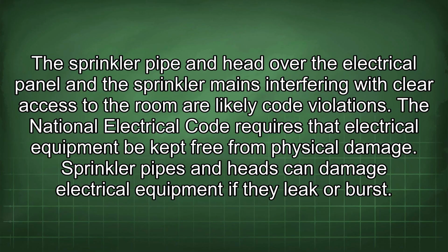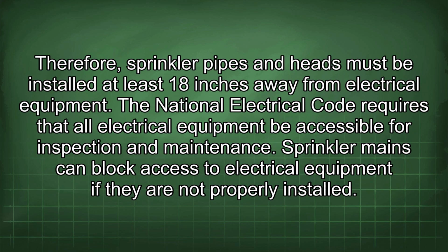The sprinkler pipe and head over the electrical panel, and the sprinkler mains interfering with clear access to the room are likely code violations. The National Electrical Code requires that electrical equipment be kept free from physical damage. Sprinkler pipes and heads can damage electrical equipment if they leak or burst. Therefore, sprinkler pipes and heads must be installed at least 18 inches away from electrical equipment.